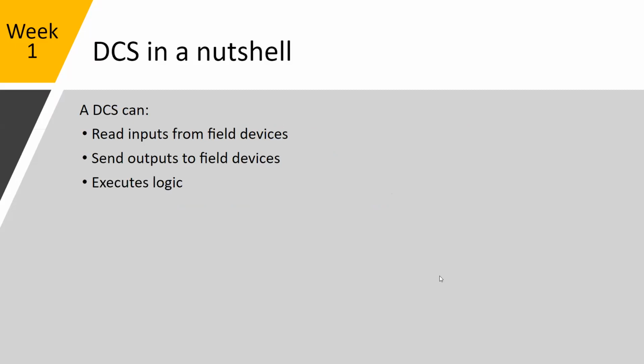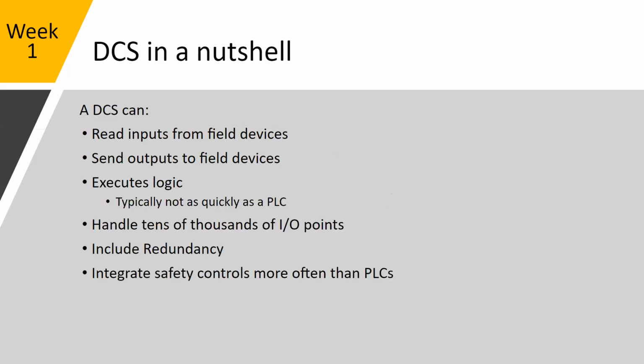So we're going to touch a lot of the basics of each of these systems today. DCS in a nutshell. They read inputs from field devices, send outputs to field devices. They'll execute logic. So that would be programs inside what to do with the information coming in and out of the field. And again, like I mentioned before, the DCSs typically handle tens of thousands of IO points.